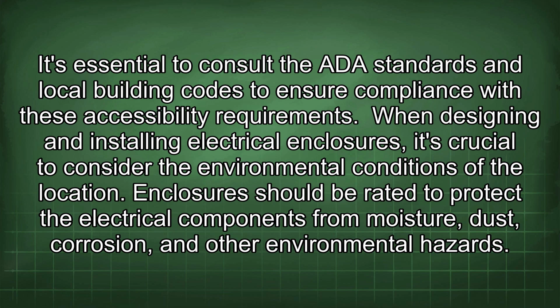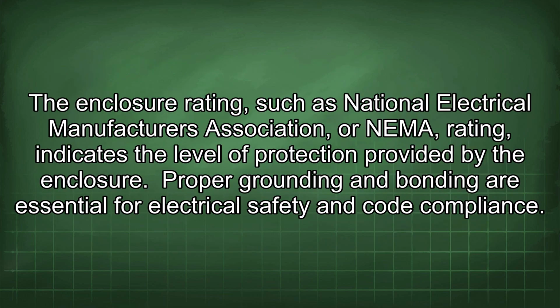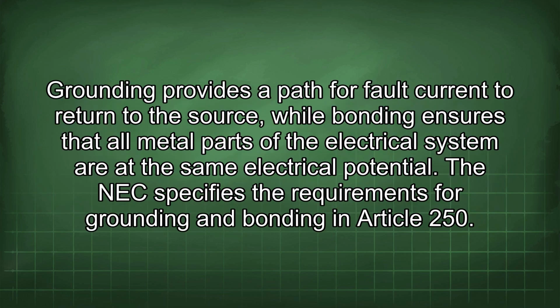When designing and installing electrical enclosures, it's crucial to consider the environmental conditions of the location. Enclosures should be rated to protect the electrical components from moisture, dust, corrosion, and other environmental hazards. The enclosure rating, such as National Electrical Manufacturers Association or NEMA rating, indicates the level of protection provided by the enclosure. Proper grounding and bonding are essential for electrical safety and code compliance. Grounding provides a path for fault current to return to the source, while bonding ensures that all metal parts of the electrical system are at the same electrical potential.